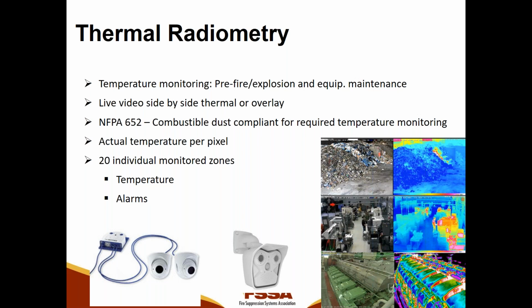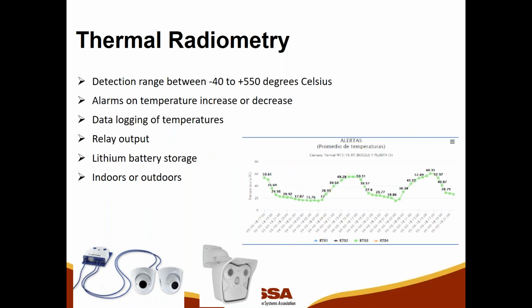The camera on the right-hand side is a video camera, and then a FLIR imager on the left. So these are the images that you get from what we call the OWL. So the detection range is wide, -40 to 550 degrees C. For each camera image, you can have up to 20 areas of interest. So each area of interest could be monitored for its individual temperature and alarm on temperature increase or decrease. And for each area of interest on each camera, you get a graph of temperature over time. So that can help with maintenance for the customers.